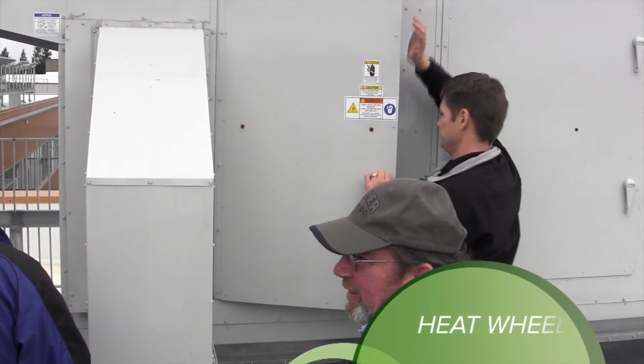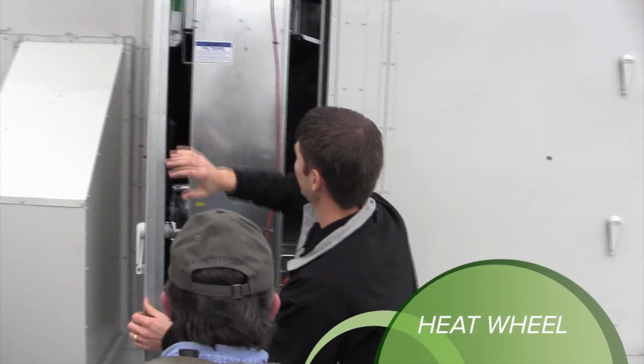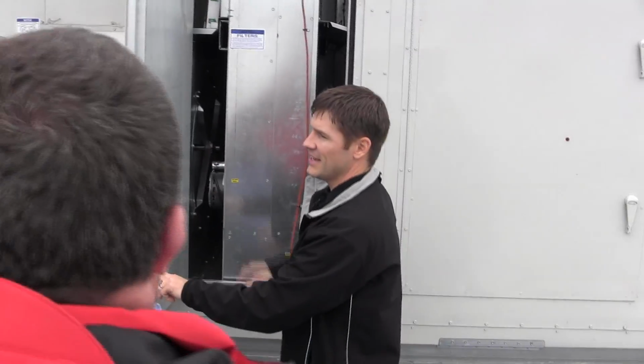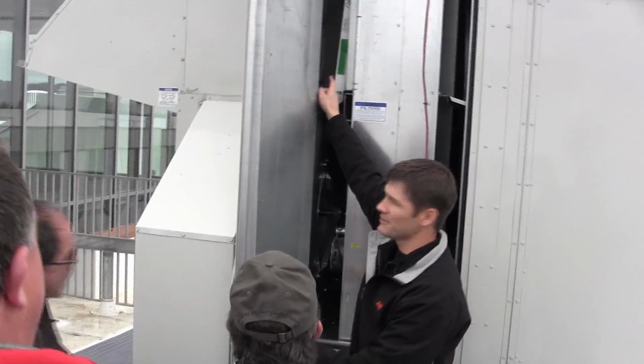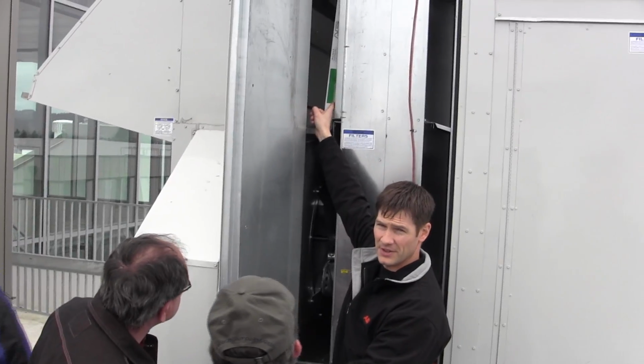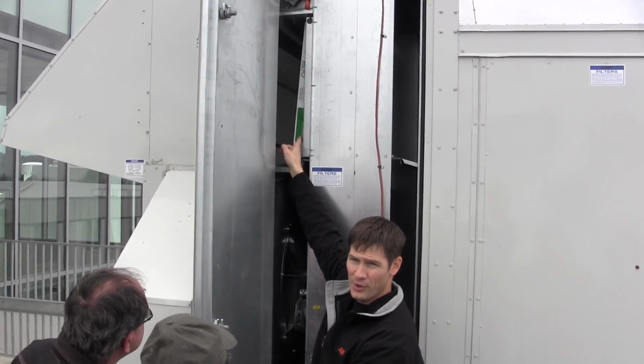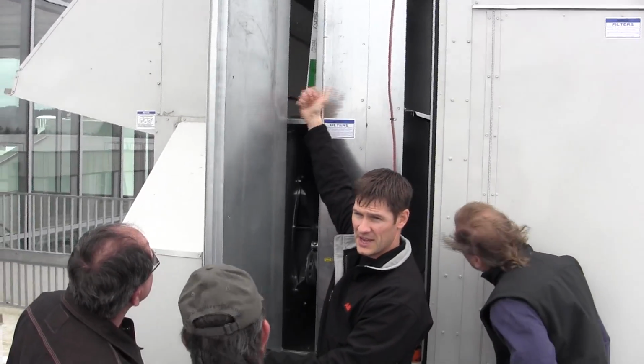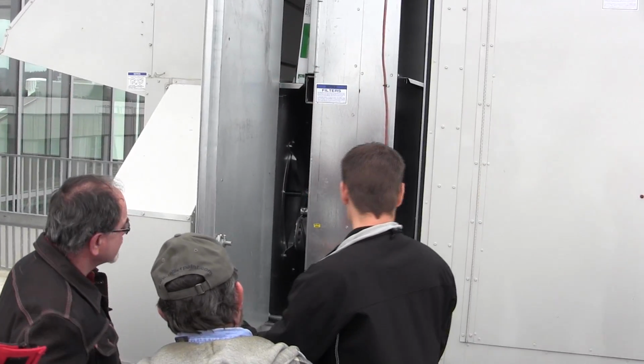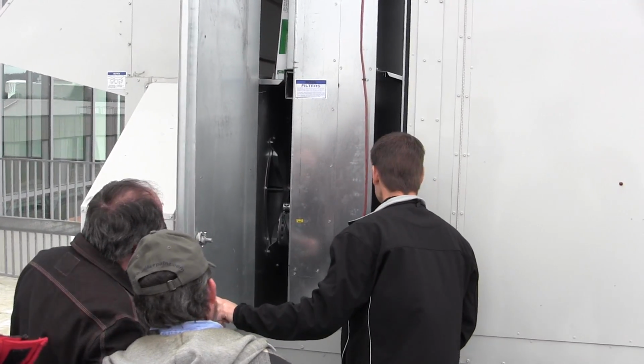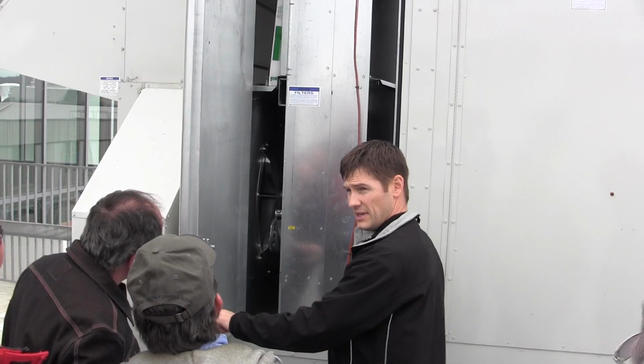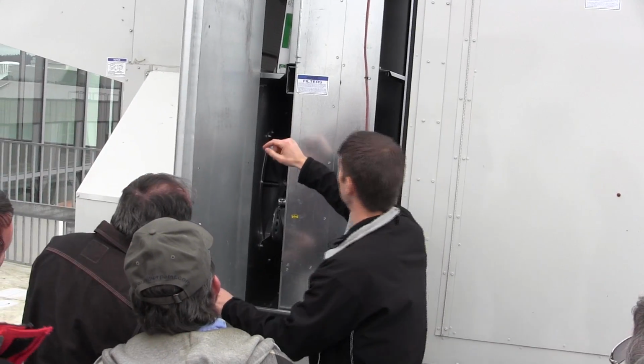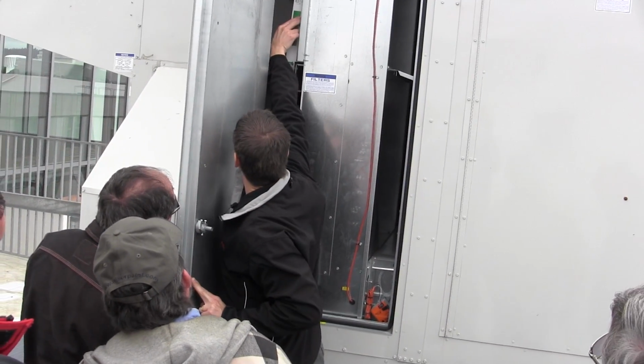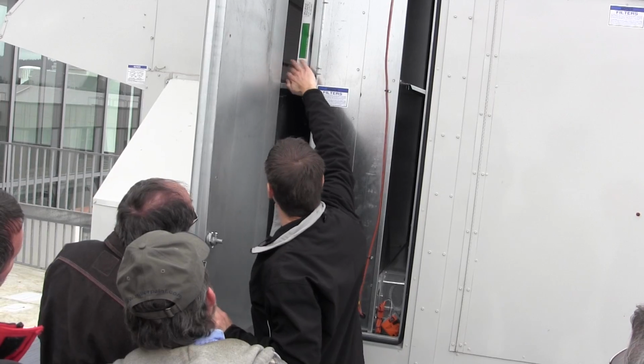So here's the heat wheel. If I could reach the top. So you can see the outside air intake on the top does have a filter rack. It's just a 2-inch filter rack. And I suggest that always be there. So it saves the heat wheel. That's pretty size filter, 2-inch? Yes. Right. Like you want to slap up on top. So. Oh. That's good. A little better.